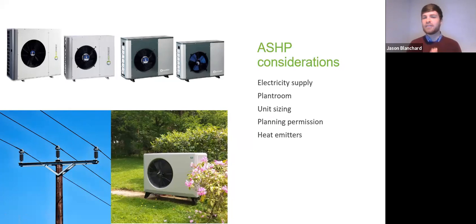An air source heat pump rated at 12 kilowatts is typically rated at around +7 degrees air temperature outside. That's not necessarily what matters for usable heat. In the UK, we want to know what that heat pump can provide at -7 degrees, or even lower—we've had a lot of snow lately, and I know places like Scotland will see it much colder. As the outside air temperature drops, air source heat pumps get less efficient and provide less heat and hot water to your home.